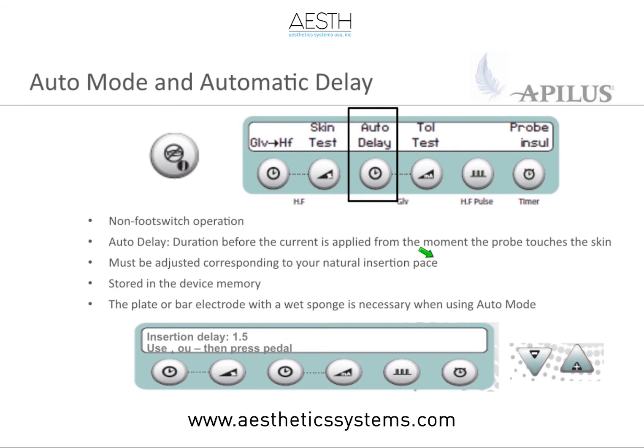Let's continue. So let's go talk about the auto mode. If you remember, the auto mode was the working without the foot pedal. So there is an auto mode key on the machine. If you don't like to press the foot pedal when you are working, then you can opt to use the pedal-less function. So auto mode, there's a button, I'll show you where it is, that turns it on. And then if you remember from the configuration menu, we could set our delay. The way that auto mode works is that your probe essentially becomes a moisture sensor. And as soon as the probe touches the top of the client's skin, it starts a countdown. This countdown is how long you need to do an insertion before the machine automatically delivers the pulses.